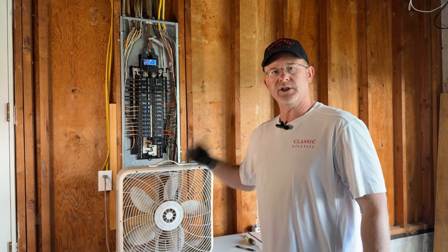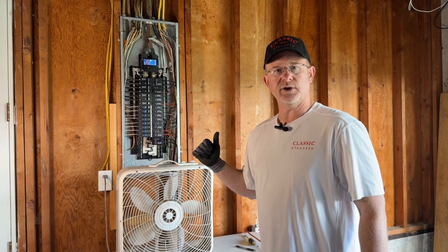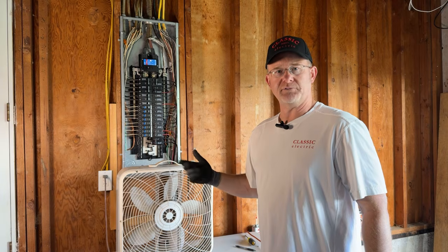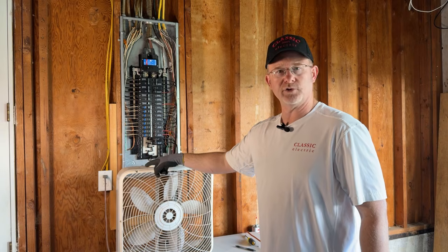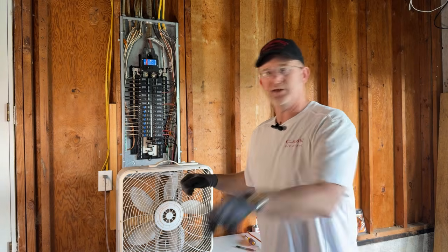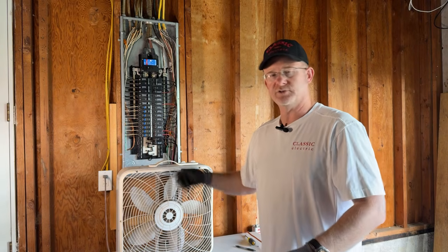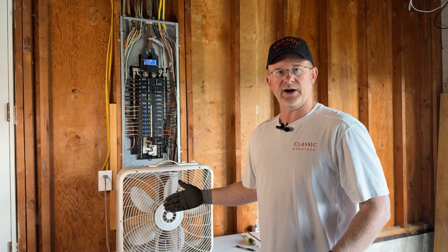So I explained to them, you're going to need to replace your pump and your water feature, and that'll cure the problem. You don't need an actual electrician in that case because we've already proved the GFCI works because you've already reset it. And then every time you go to plug something in, it trips. So it's not the GFCI. The GFCI is doing its job.